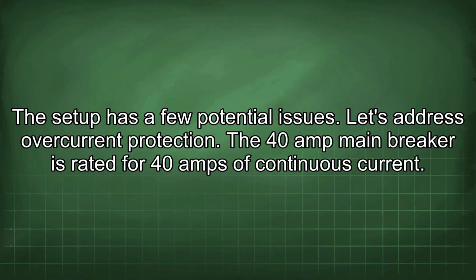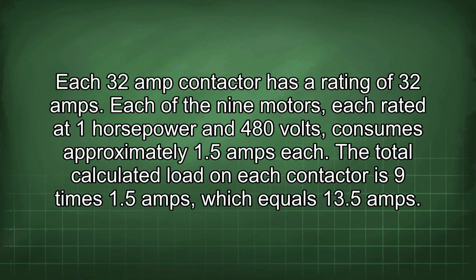The setup has a few potential issues. Let's address overcurrent protection. The 40 amp main breaker is rated for 40 amps of continuous current. Each 32 amp contactor has a rating of 32 amps. Each of the 9 motors, each rated at 1 horsepower and 480 volts, consumes approximately 1.5 amps.